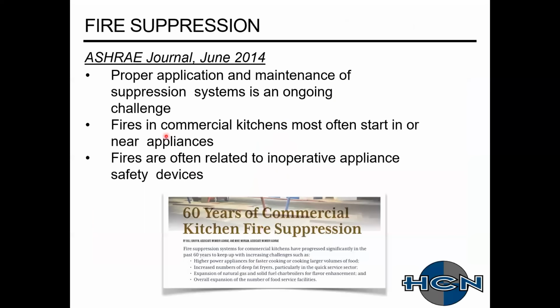Same one here. An ASHRAE Journal article from 2014 did a comprehensive 60-year review of what fire suppression systems have been doing. Not a ton has been evolving, but there are some system manufacturers now that are using a water-based system. Yes, water, kitchens, fires, I know that doesn't sound right, but they use a surfactant, so kind of a soapy material, and then the way they discharge the nozzles at the equipment. And it's UL 300 approved.